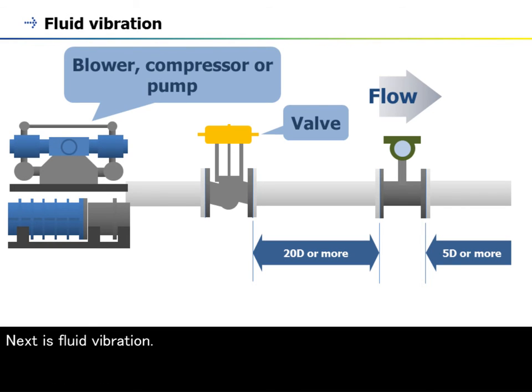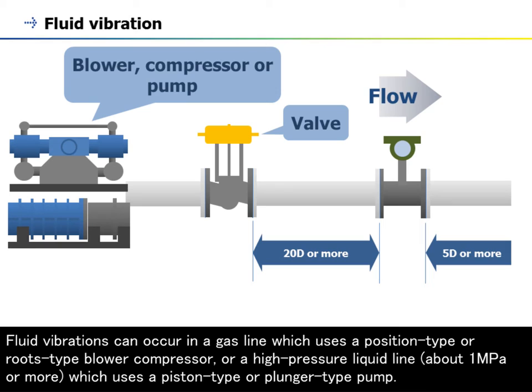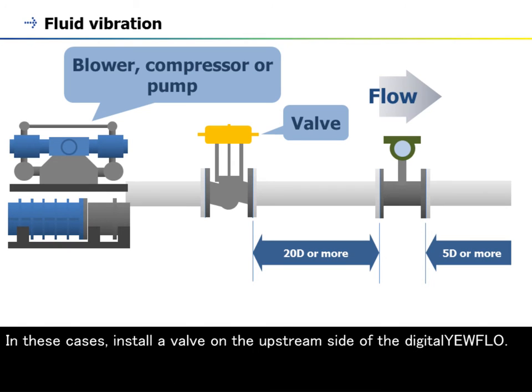Next is fluid vibration. Fluid vibrations can occur in a gas line which uses a position type or roots type blower compressor, or a high pressure liquid line, about 1 MPa or more, which uses a piston type or plunger type pump. In these cases, install a valve on the upstream side of the digitalYEWFLO.